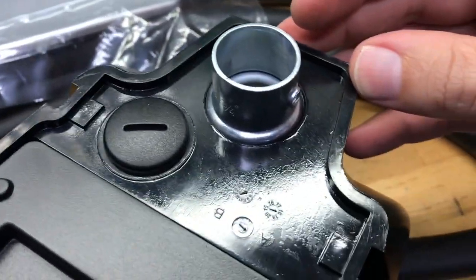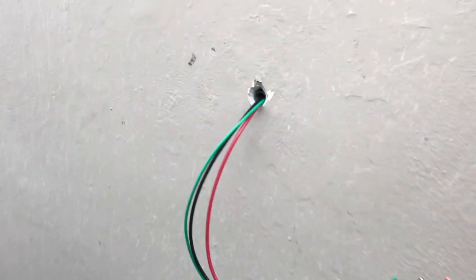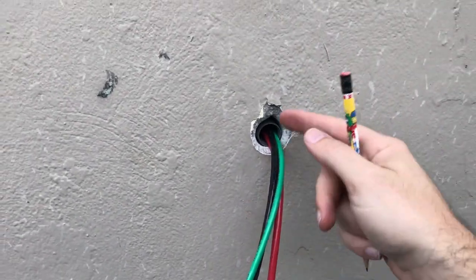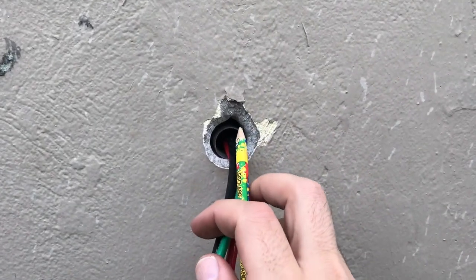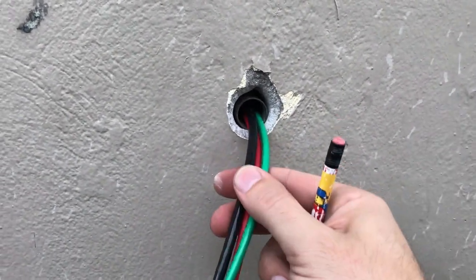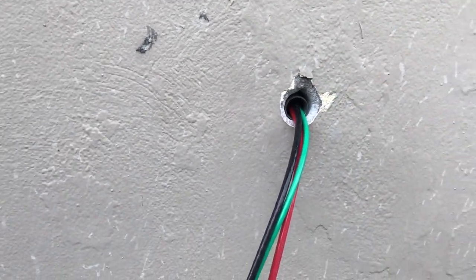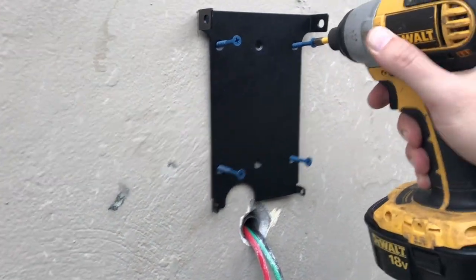Here's the wall side of things. Last weekend I ran this three-quarter-inch conduit, drilled this hole, chamfered the edge with a chisel, and made a little notch for the set screw indentation. We're going to center it up and mark the mounting location. My favorite fastener for concrete: Tapcon.